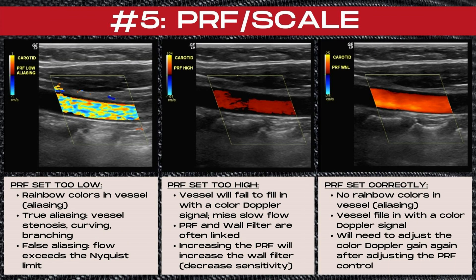The next step in our color Doppler optimization checklist is the PRF or scale control. Doppler has a limit, and past this limit the ultrasound machine can no longer measure the velocity of flow because it is too high — this is known as the Nyquist limit. The Nyquist limit is the maximum limit of the Doppler shift that can be measured and displayed by the ultrasound machine. Above this Nyquist limit, aliasing occurs. The Nyquist limit is half of the PRF. Aliasing is flow that changes speed and direction either due to vessel dynamics or improper color settings, and it appears as multiple colors displayed within a structure or vessel on color Doppler. Artifactual velocities occur when the velocity of flow has exceeded the Nyquist limit.